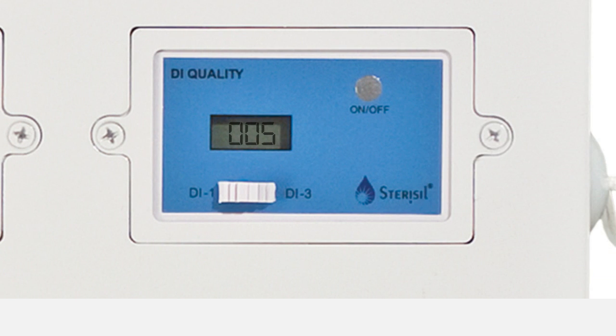The next blue monitor is used to monitor the water hardness after the first stage, DI1, as well as the autoclave water quality, DI3. To switch between the DI1 reading and the DI3 water reading, move the white switch from left to right. This monitor can also be used to troubleshoot the system. The ideal ranges for this monitor are as follows. For DI1, this monitor should read below 10 parts per million TDS.